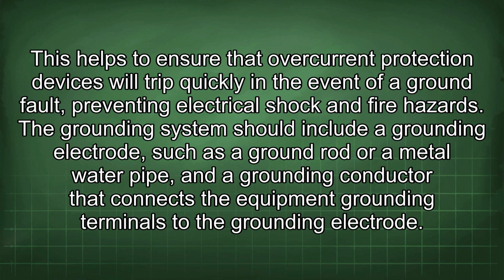This helps to ensure that overcurrent protection devices will trip quickly in the event of a ground fault, preventing electrical shock and fire hazards. The grounding system should include a grounding electrode, such as a ground rod or a metal water pipe, and a grounding conductor that connects the equipment grounding terminals to the grounding electrode.